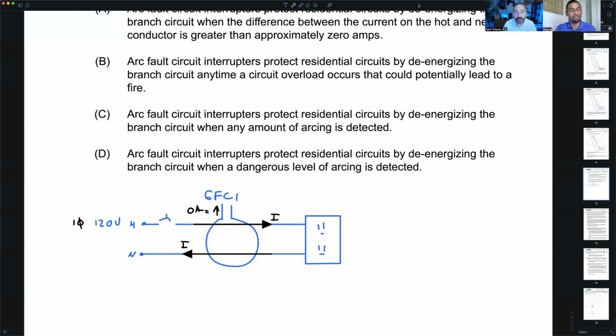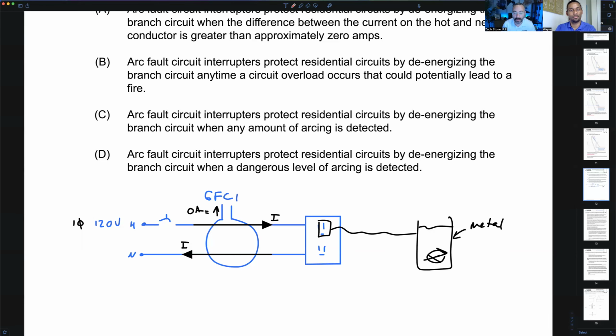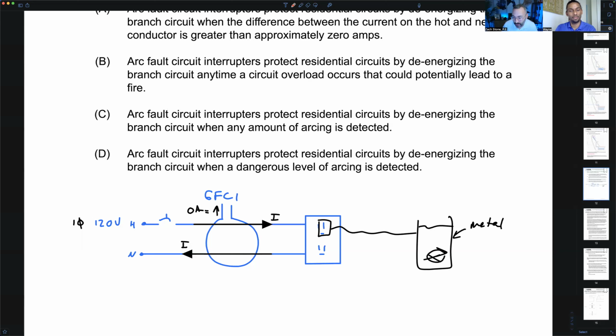Now, if I got a ground fault, say something's plugged into this. Maybe it's a blender whizzing around making a protein shake. Say it's a metal case, like a metal blender. And what if the internal wires come into contact with the metal case? We're going to have a ground fault. What we didn't show is that we do actually have a third conductor, a third ground conductor. So now I've got a ground fault.